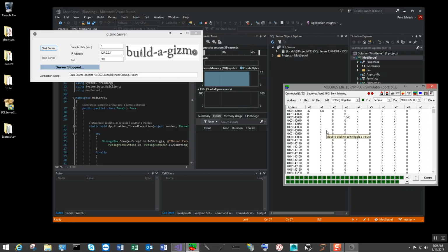And to actually understand full offsetting in Modbus is very important, because sometimes you're getting a Modbus map from a device that doesn't start directly at the first address. It may start down in the 41,000 territory, somewhere further in the map, and you'd want to offset all your data to it. Standard Modbus exercise in the engineering world.